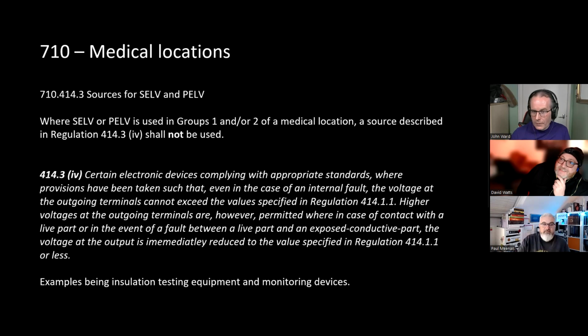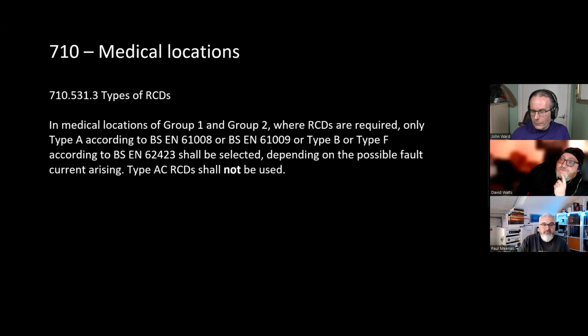This looks familiar. That's the same one for medical locations, yes, for your requirements of SELV and PELV. There is a certain amount of copy and paste, yeah. Right, RCDs, what have we got here? Medical locations of Group 1 and Group 2. Without going into too much detail, that's where we're going to use applied parts for the treatment. In Group 1, the loss of power will not create a risk. In Group 2, the loss of power will be a risk to the patient. In either of those, RCDs will be required. Only Type A, B, or F are suitable. No AC RCDs are suitable. Which is marvelous. Marvelous. Yep.